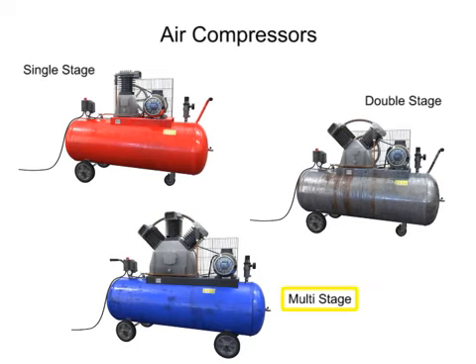On these larger compressors, cooling may take place by circulating water instead of air. To reach a pressure of 2500 PSI, as many as six or seven stages may be needed with cooling between each stage.